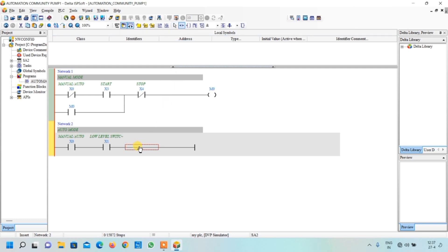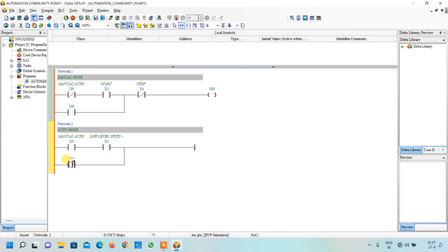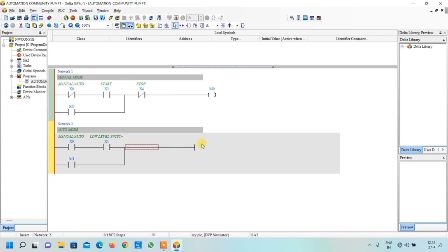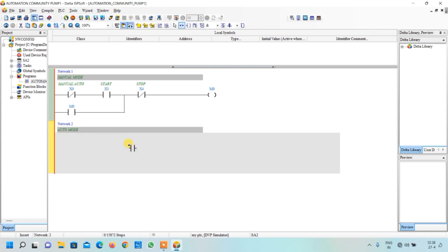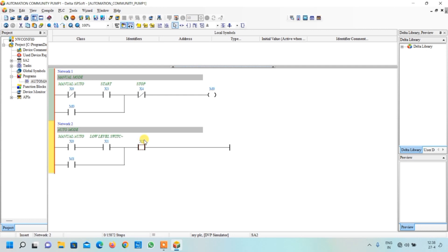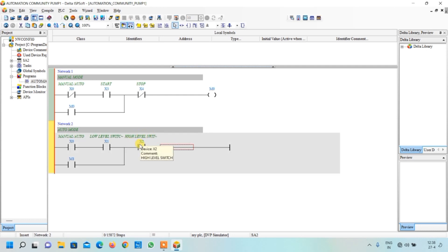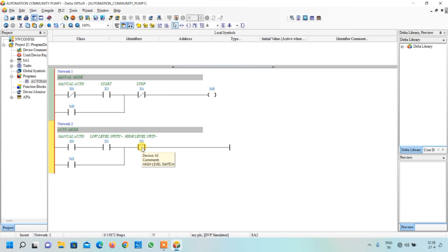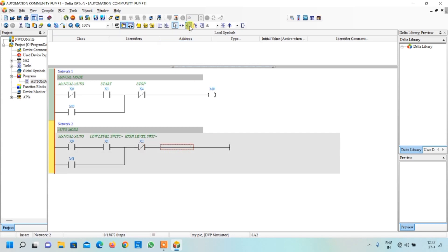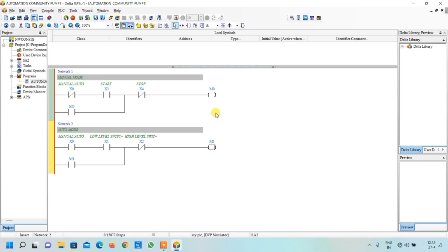We then add a parallel path for latching the output, naming that contact M1. Next, we add the high level switch contact in series, naming it X2. When the high level is reached we want to stop, so we select it as NC — press Space and click NC. Finally, we add the output coil and name it M1. M0 and M1 are internal relays of the PLC.